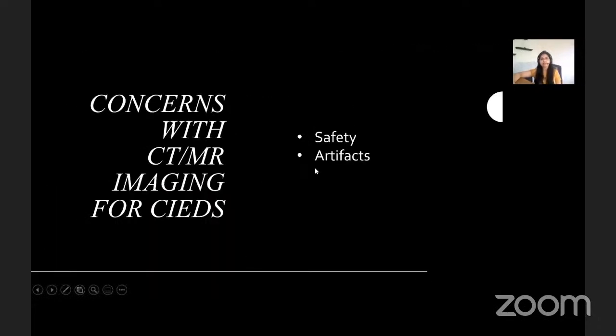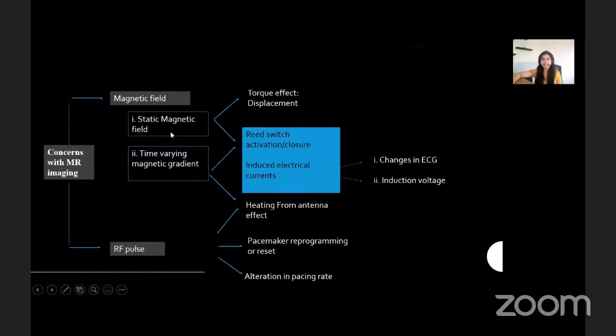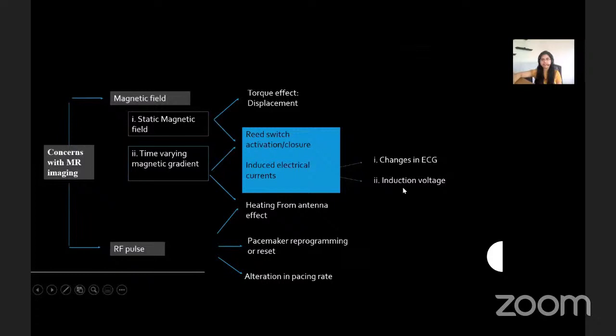Once implanted with a device, patients who need CT or MR and their clinicians must deal with concerns related to safety. The radiologist may face issues with imaging artifacts that appear due to in-situ devices. Static and time-varying magnetic fields were proposed to cause displacement of the device, activation of the reed switch causing unintended cardiac stimulation, and induced electrical currents that can generate induction voltage and cause premature battery depletion. RF pulses can cause heating of the leads, device reprogramming, and alteration in pacing rate.